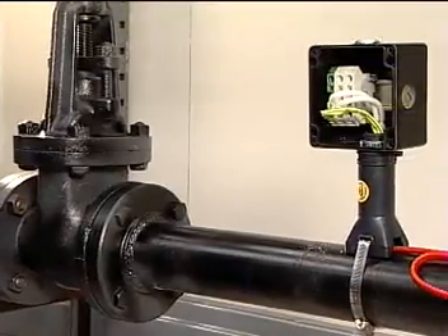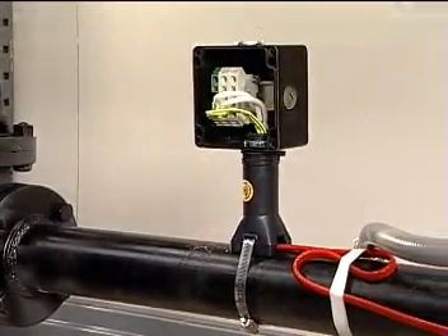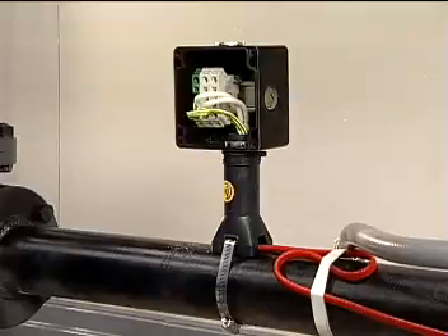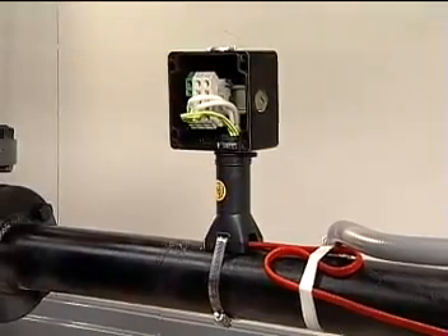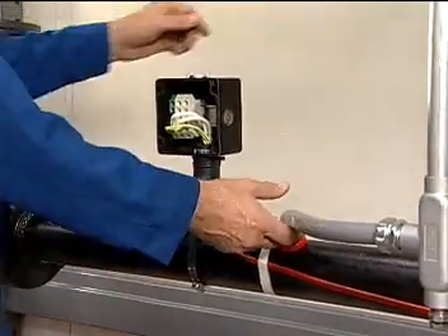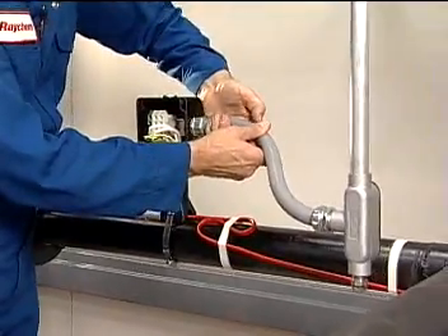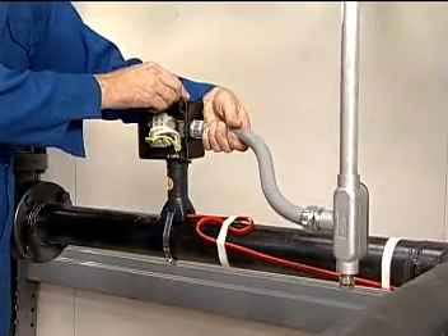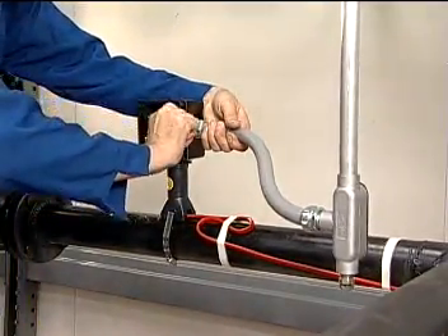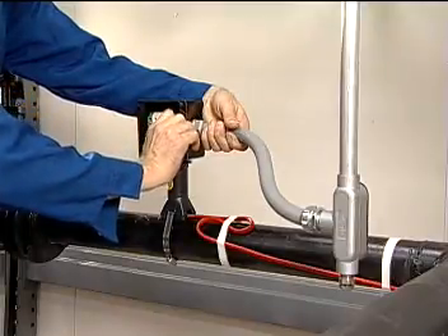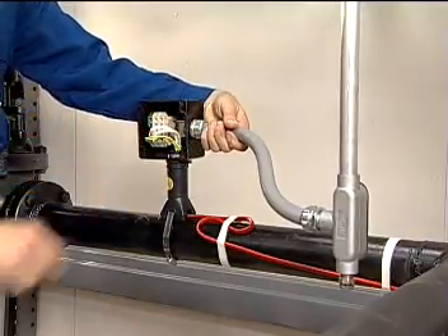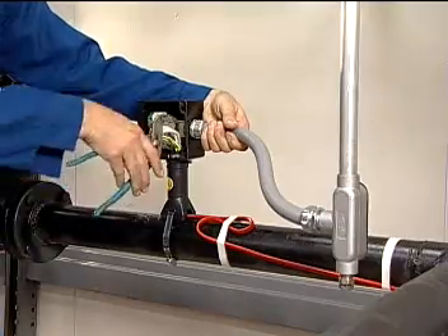Try to mount the power connections, boxes, and drains where they will be accessible but out of the way of foot traffic and equipment. Mount the power connections so that they are not at the low point of the conduit system. Be sure to install the conduit drain provided in the kit. Also, make sure the cable is inserted into the stand before mounting because it's not possible to do so once it's been attached to the pipe.